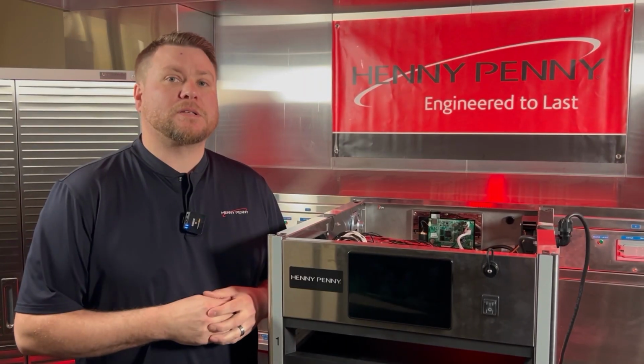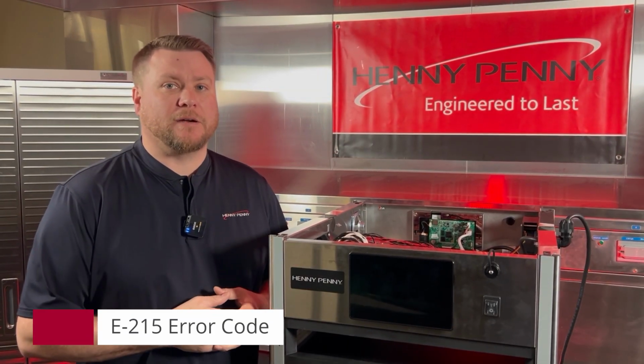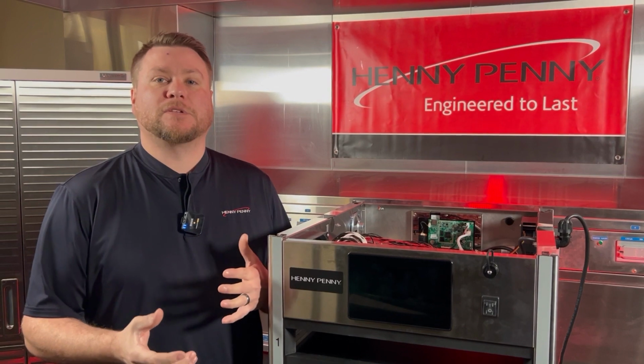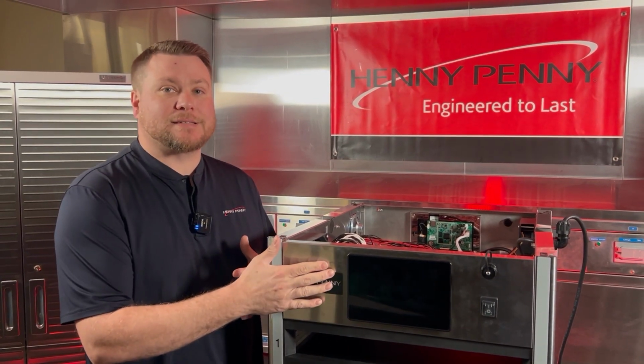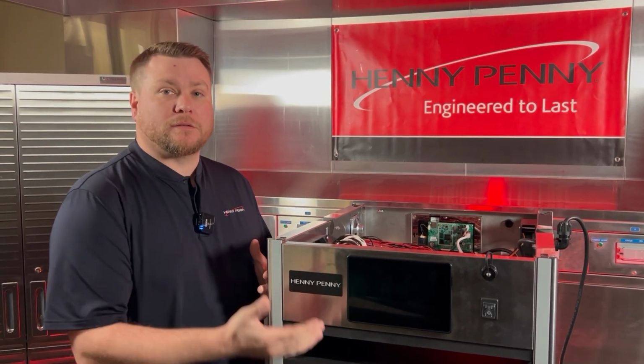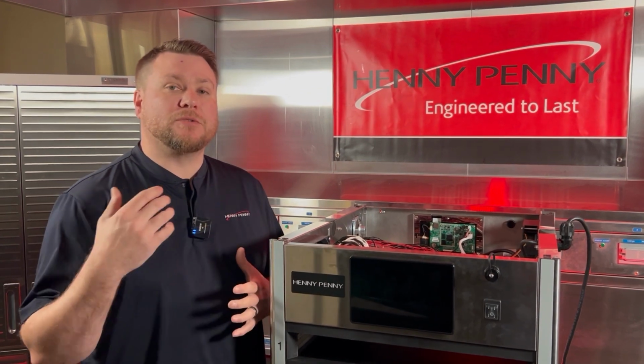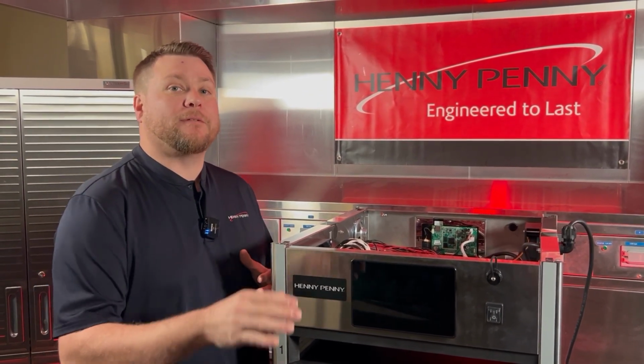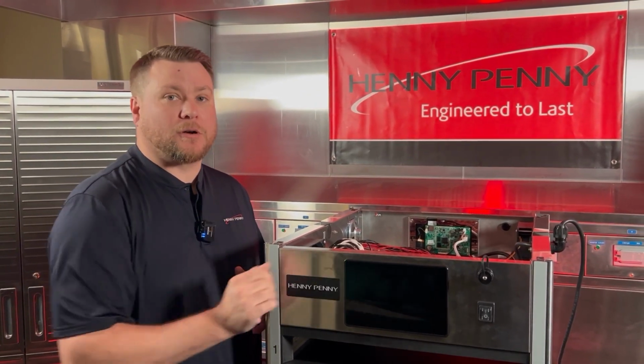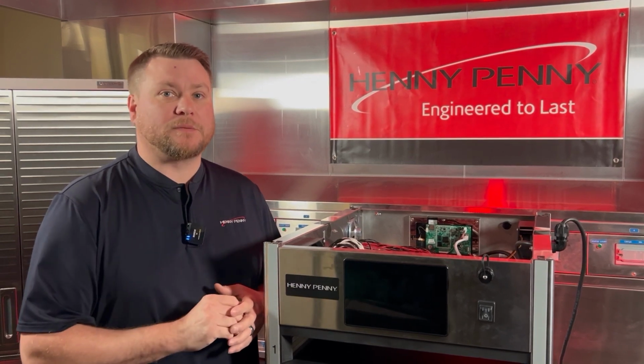In this video, we're going to talk about the E-215 error code. Now, this error code comes up when the control has not seen one of the shelves come up to set point temperature within 50 minutes after startup, and that's with uninterrupted power.